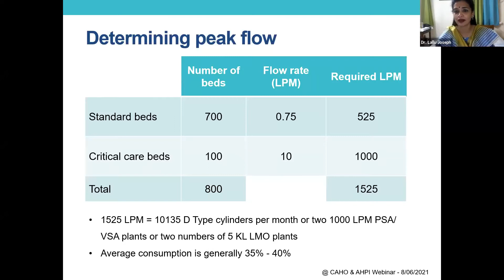You can plan to have 10,135 D-type cylinders per month, or two 1,000 LPM PSA plants, or you can have 5 KL LMO liquid medical oxygen. Now here, the decision is up to the administrators. Am I going to indent for 10,000 D-type cylinders? Is it feasible for me to go for an LMO plant? And I'm sure Dr. Sujit will be talking about that. So average consumption is generally 35 to 40%, but you plan for 100% load.